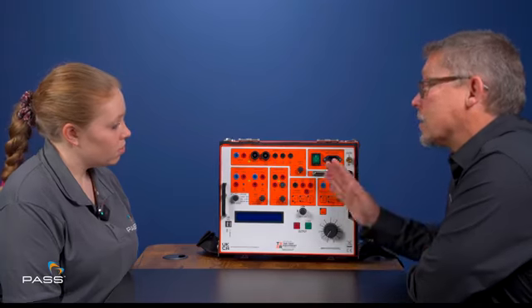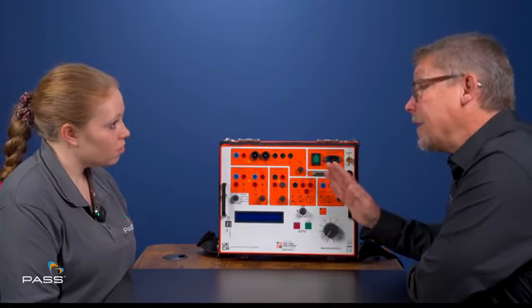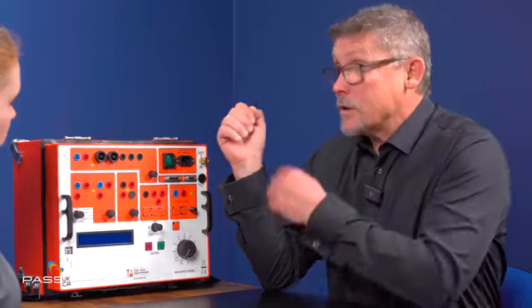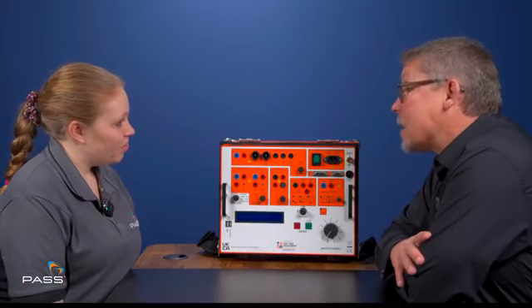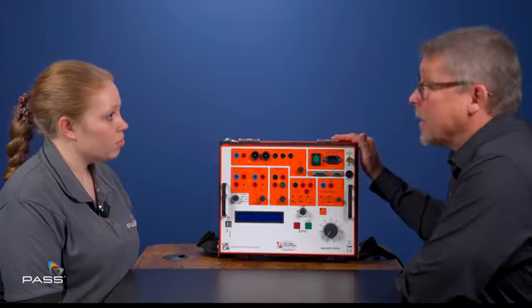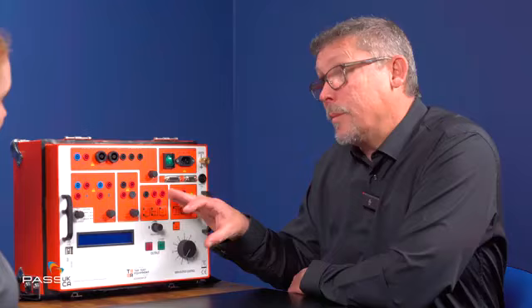The unit itself also monitors the total VA of what's going out, and if it sees an excess, it will trip out. So these things have a duty cycle. A duty cycle is so long on for so long off. Now, most engineers ignore that. They get it in the manual and it'll be clearly laid out. We know that. So what we've done is we've programmed the unit to monitor itself. And if it's exceeded, then it will come up and say duty cycle and basically won't allow you to do anything till it's cooled back down again. Now, that is a saving grace for this unit. And to be fair, many current injection test sets will do the same sort of thing. But it's one way of making sure that your investment in your test equipment is well looked after.